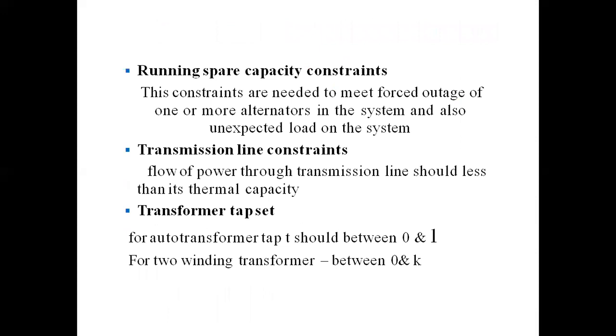There are running spare capacity constraints. These constraints are needed to meet forced outage of one or more alternators in the system and also unexpected load on the system. Another is the transmission line constraints — flow of power through the transmission line should be less than its thermal capacity.